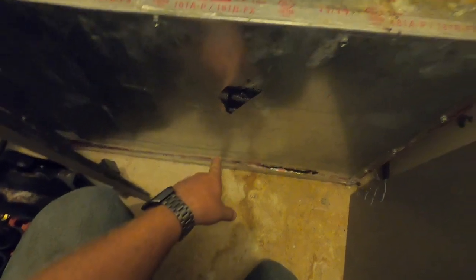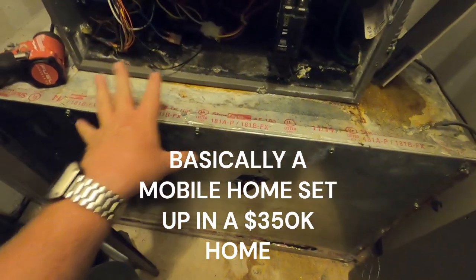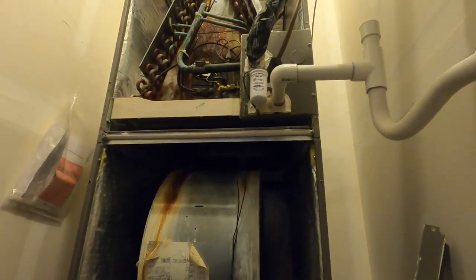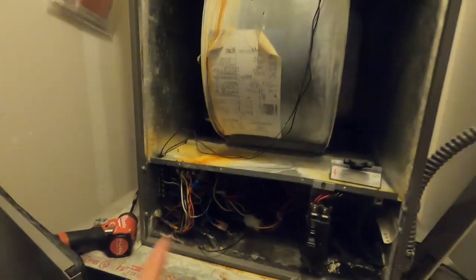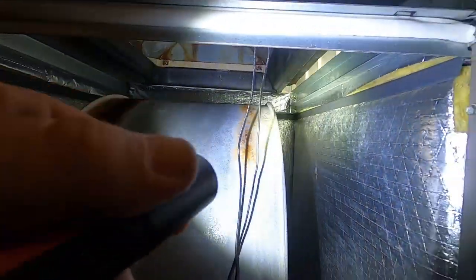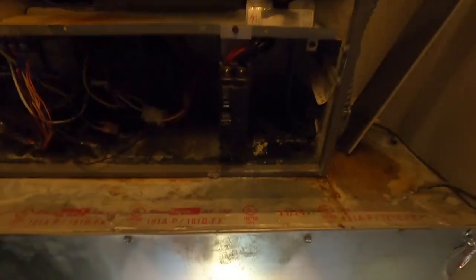Obviously, as you can see, there's no drain pan because it's downflow, plenum, no anything to prevent water other than this. And you guys saw the stain on the ceiling down there. And I haven't checked the charge outside yet, but typically what we've got, if you look in here, and I don't know where my light is, water's been dripping off this coil onto the blower motor, running down in here, getting into the plenum, leaking, and going through the ceiling.